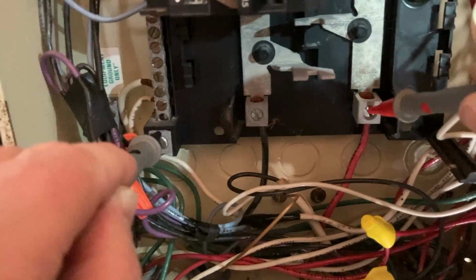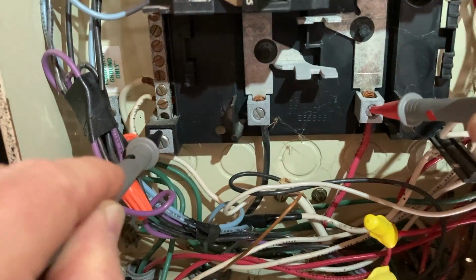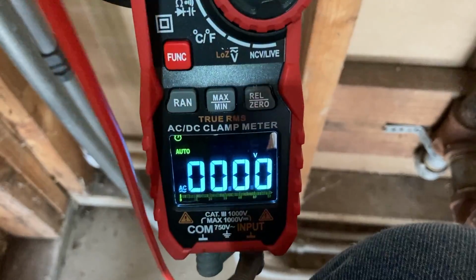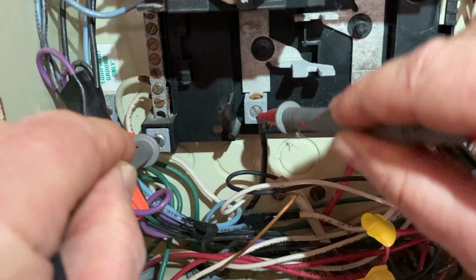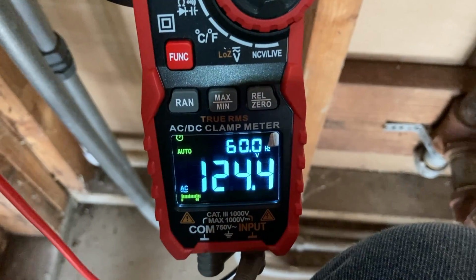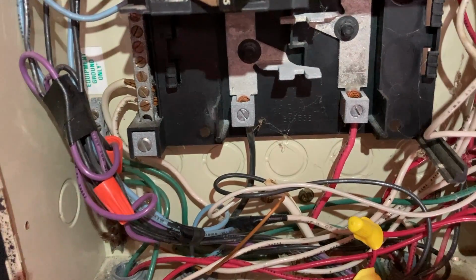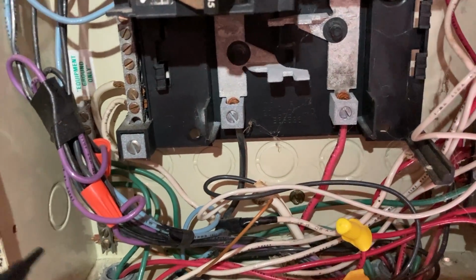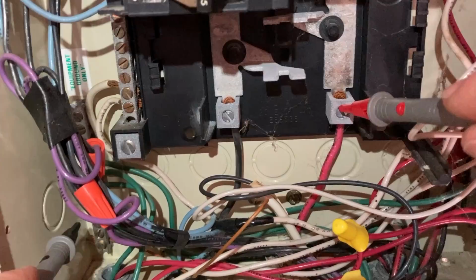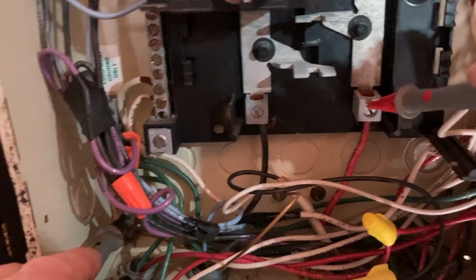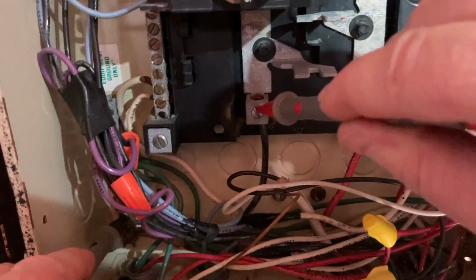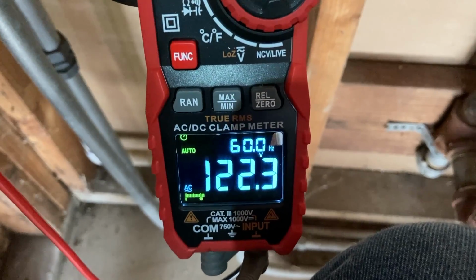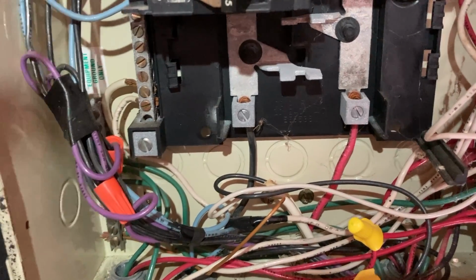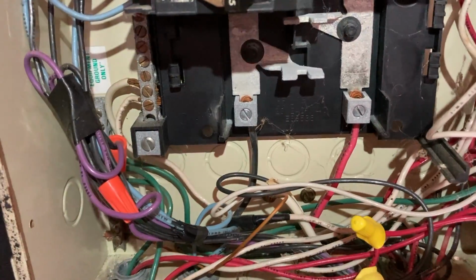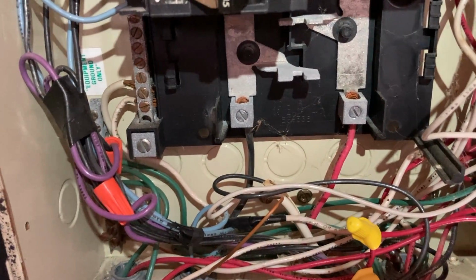And from this leg... come on, oh that's weird. There we go, 121. This leg is 124. Okay, and then let's check to ground: 122, 123. When the power's off, I'll make sure the neutral bar is disconnected from the ground, the cabinet, because this is a sub panel, but it looks like it is—it's floating on top of the plastic there.